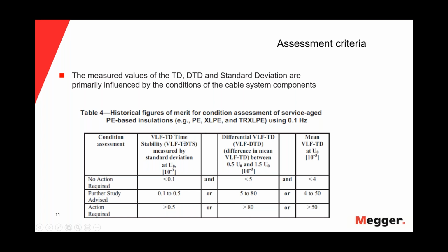And then VLF TD time stability would be, of course, the standard deviation: less than 0.1, no action; 0.1 to 0.5, further study advised; and then, of course, greater than 0.5, action required.